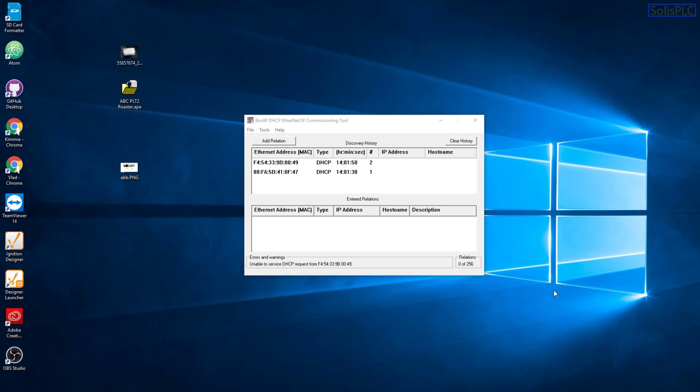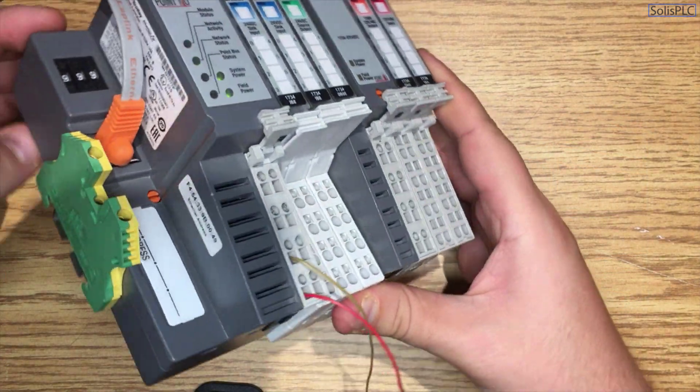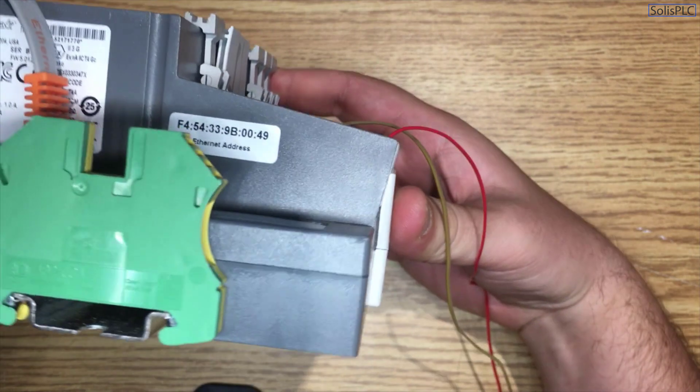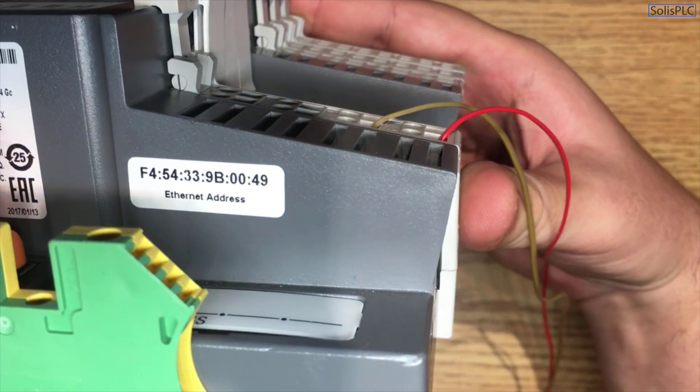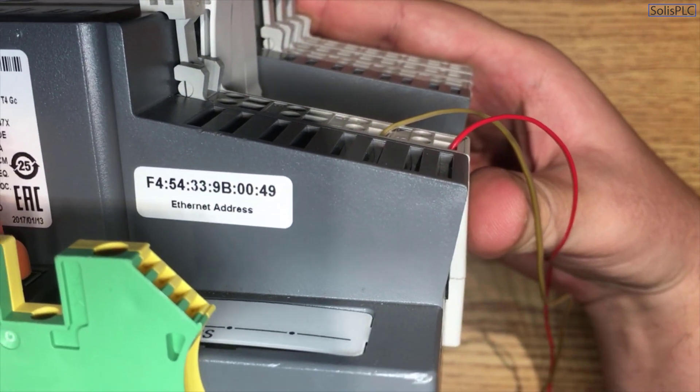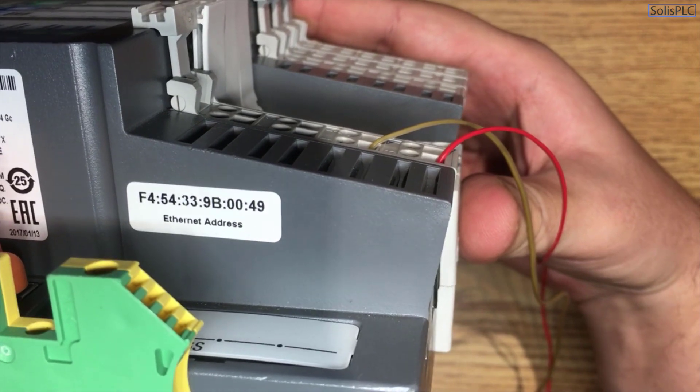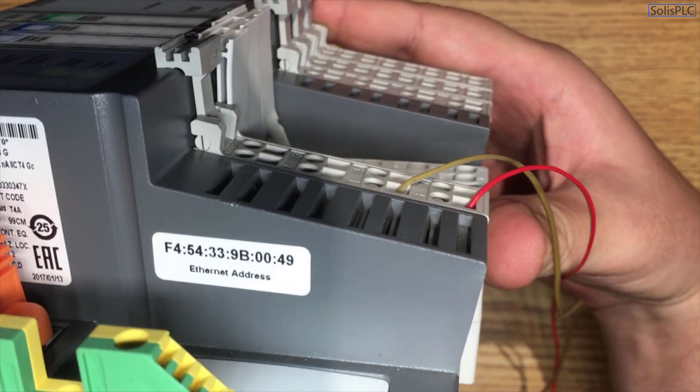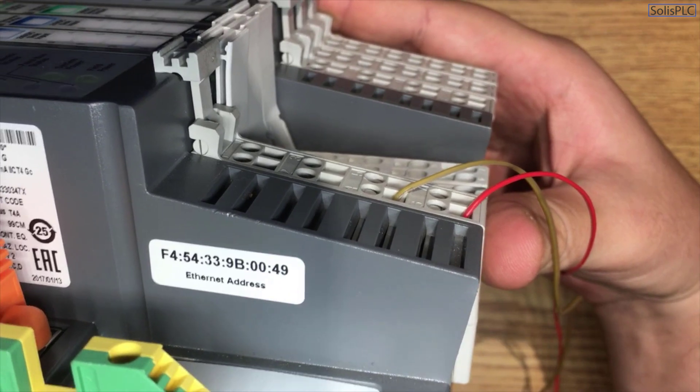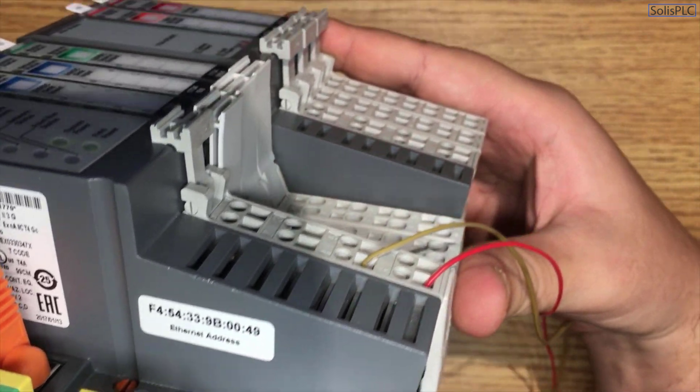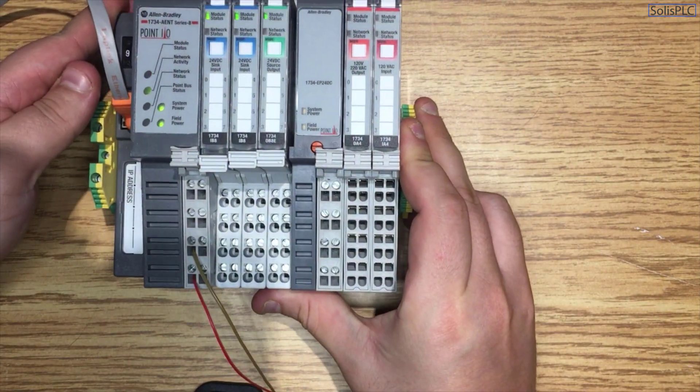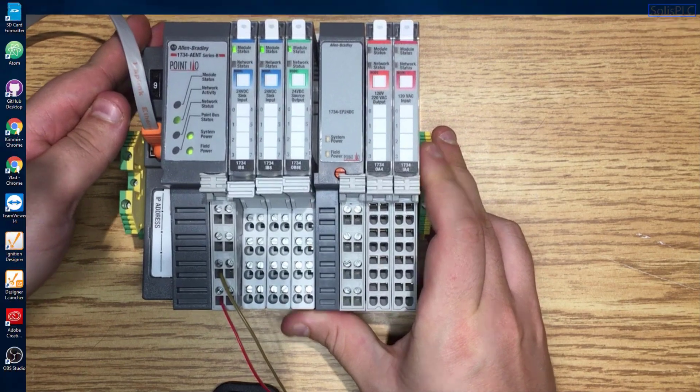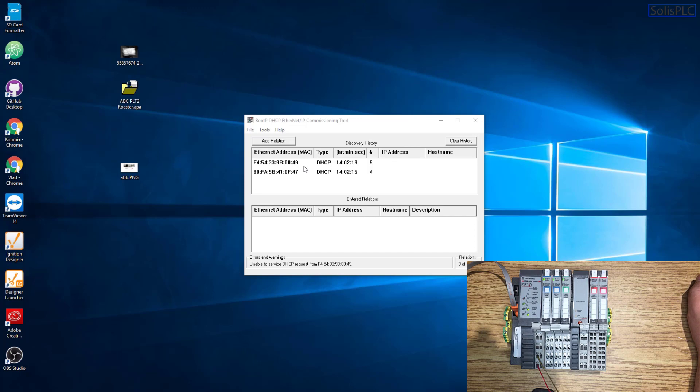So I did forget to mention one important detail, and that is the fact that your BootP tool will find a lot of different MAC addresses, especially if you're connected to a network with other devices. In order to make sure that you're using the right MAC address, you do need to look on the side of the module. And once we zoom in, you will notice that there is going to be a MAC address sticker and it's going to indicate F4, 54, 33, 9B, 00 and then 49. So that specific MAC address needs to match what you select in your BootP utility in order to make sure that you're going to give the IP address to the right module and not something else on your network.